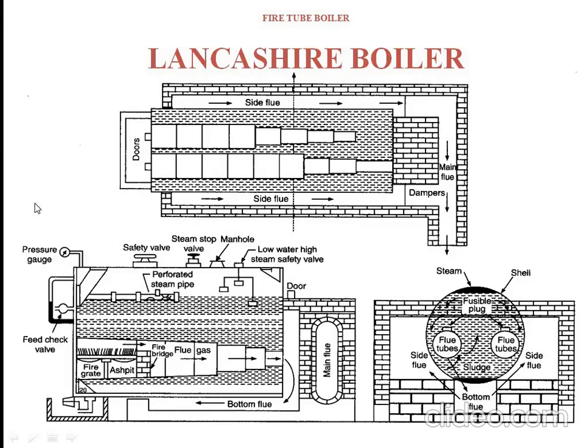Coming to the parts: there are two large fire tubes, one here and the second here, and for each fire tube there will be a grate at the starting. Over the grate, we are going to burn coal in the presence of air. After the grate, there is a fire bridge. The main use of this fire bridge is that it prevents coal or ash from entering into the tubes. At the same time, it deflects the flue gases in the upward direction.